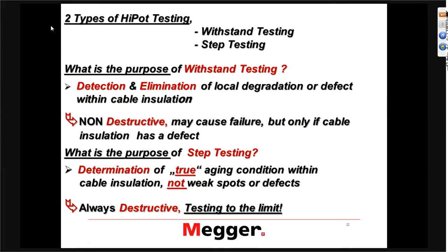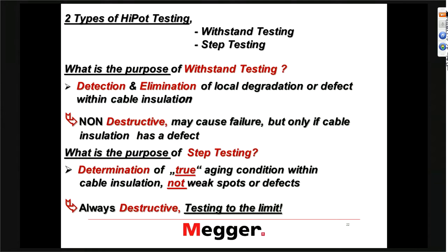Two types of HiPot testing: withstand testing and step testing. The purpose of withstand testing is detection and elimination of local degradation. It's non-destructive — I want to emphasize this. A withstand test is a non-destructive test. The cable might fail, but it fails because it has a defect. That is in stark contrast to a step test, which is also a HiPot test. The step test is the determination of the true aging condition of the cable, and it's always a destructive test because you have to test it until failure.